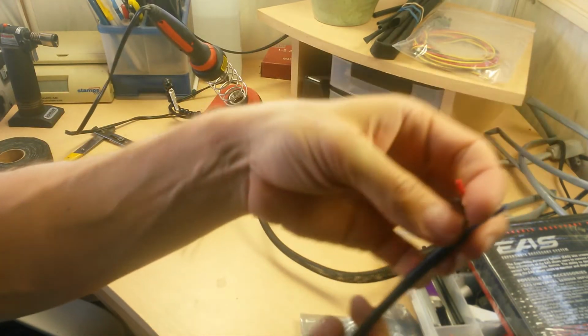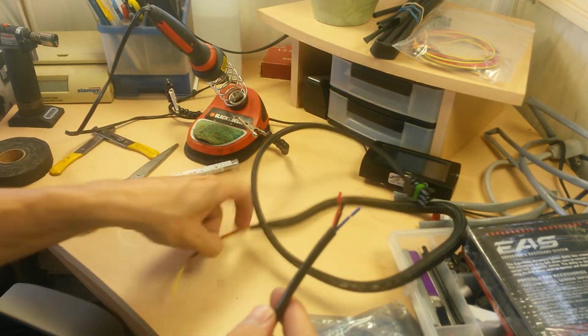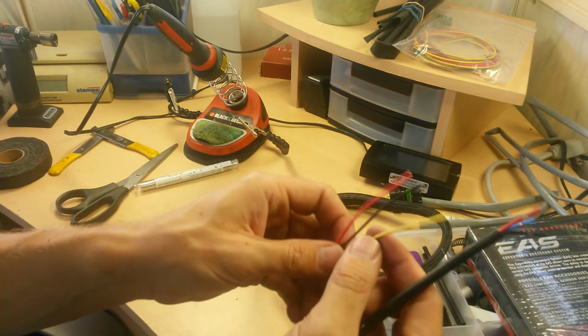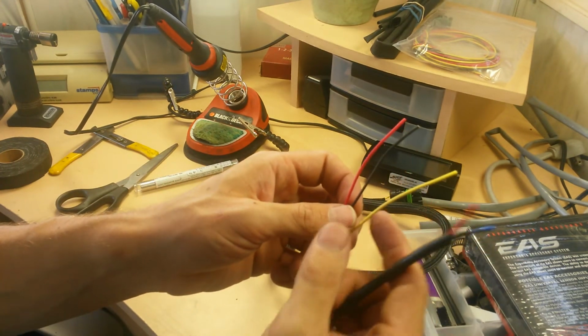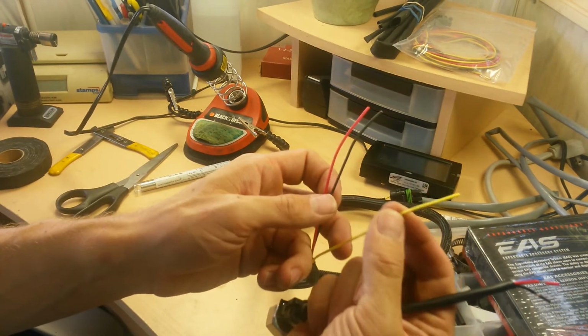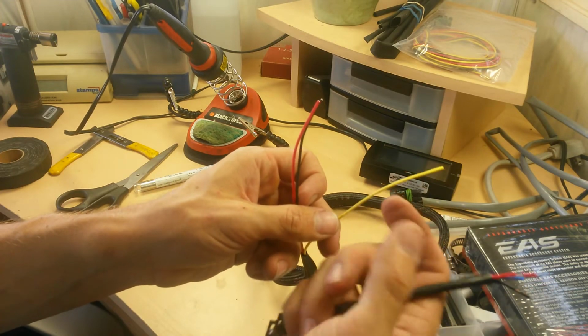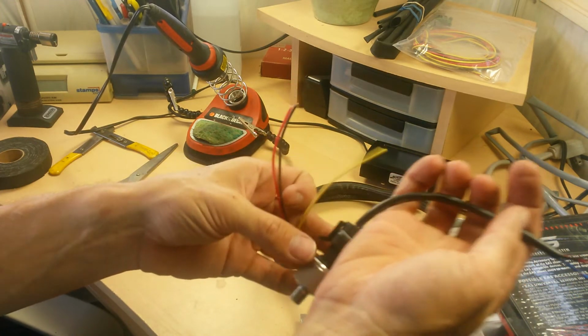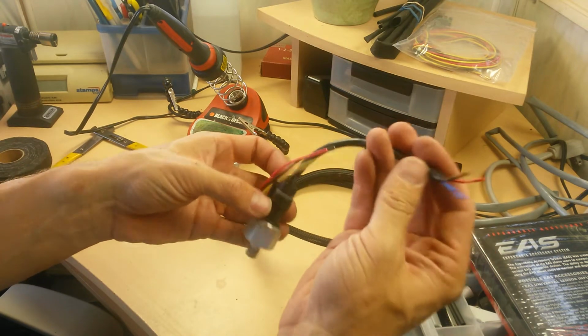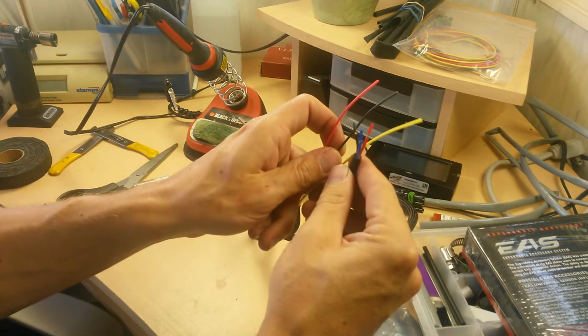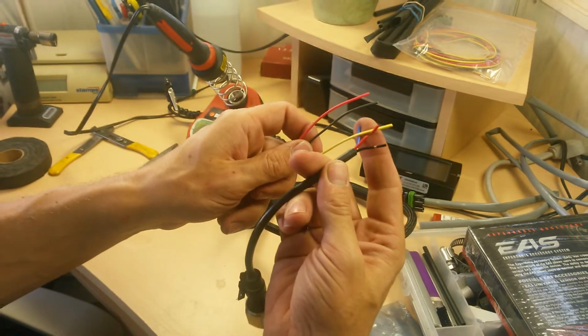So your sensors are going to come with a red, a black, and a blue wire. And your EAS system is going to come with a red, a black, and a yellow. Basically, on the EAS system, the yellow is your sensor return or signal return wire, and on the sensors, the blue wire is that same thing. So you're going to match red and black, and yellow and blue.